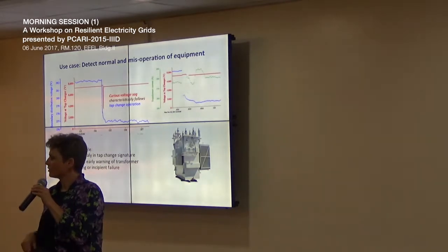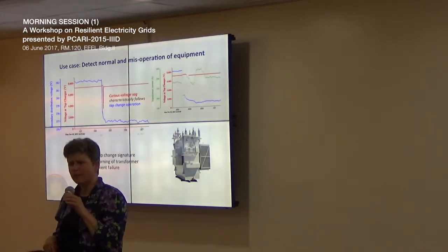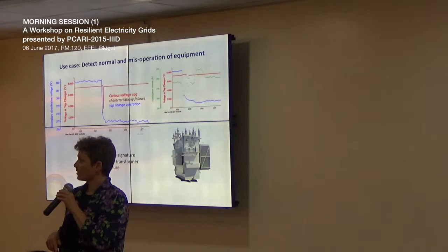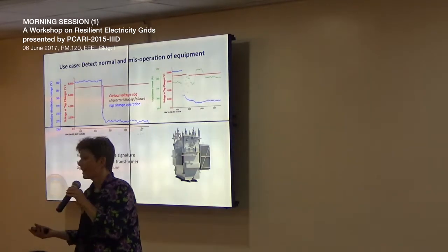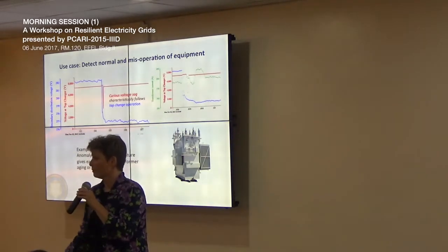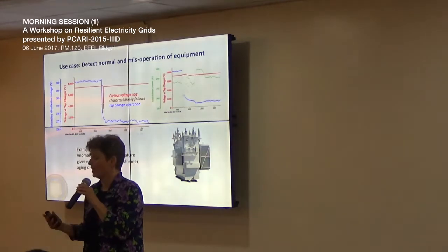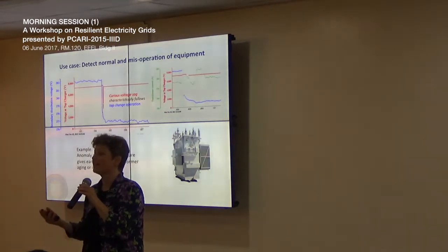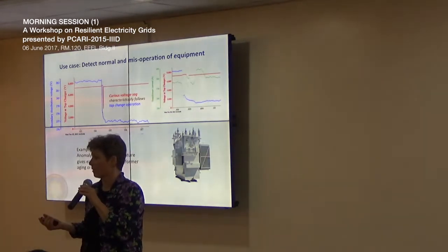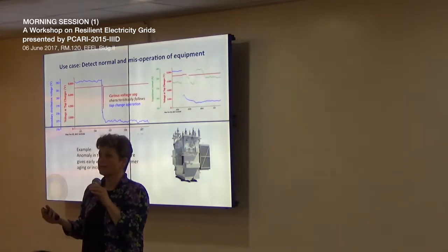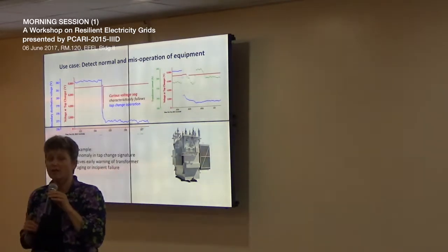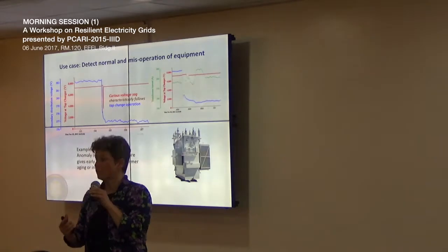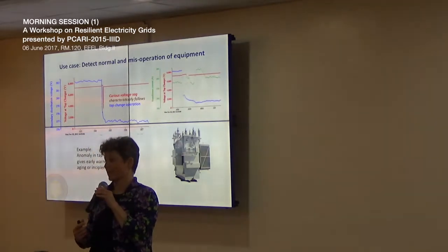We showed this to the utility and they said, that's really weird, let's go look at this transformer. They drove out there and it had a puddle of oil below it and was not feeling well at all. They said, wow, are we glad you told us this transformer has a problem, because we need to do some maintenance on it, and this would have cost us a lot of money if we hadn't known about it.